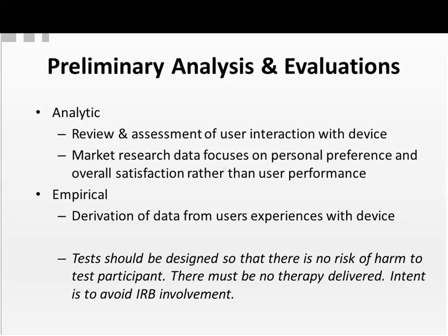Empirical is derivation of data from users' experience with the device. These are things like focus groups. Now keep in mind, for empirical studies, you want to design these studies so there's no risk or harm to test participants. You cannot deliver any therapy to the participant. You don't want to be in a situation where you should have had an IRB for the analysis.